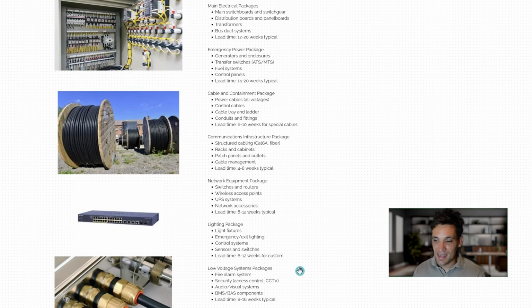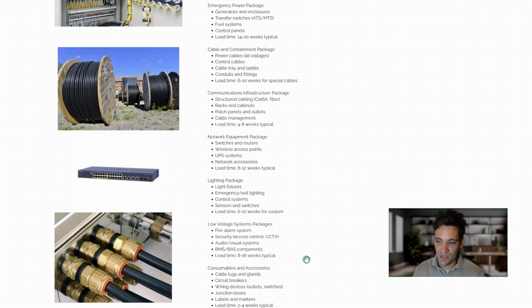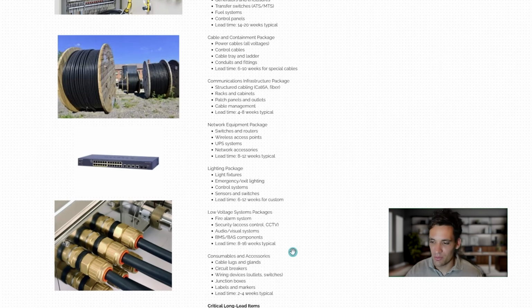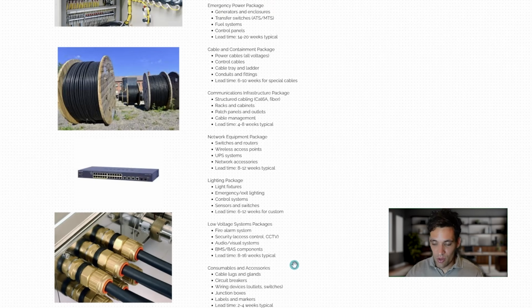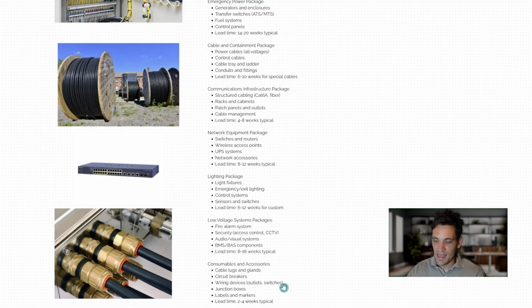Network equipment, again, can have quite a long lead time, but that'll be all the switches and routers, the racks, any separate UPS system you have for the network equipment. Then you'd order all the lighting. So you'd need the light fixtures, emergency lighting, a lighting control system, any sensors and switches. Typically go to one lighting supplier for the whole package because you often can't mix vendors with different products. Then any of the low voltage and communication system packages such as the fire alarm system, security, the audio visual, BMS, and then finally you'll probably go to a local electrical wholesaler for all the consumables and accessories.